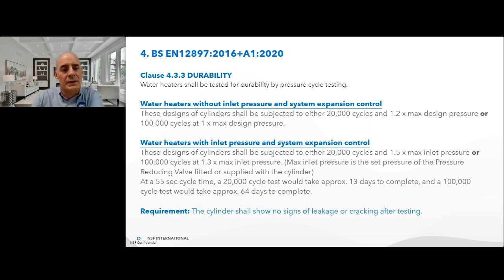So these are water heaters with inlet pressure and system expansion control. These designs of cylinders should be subjected to either 20,000 cycles at 1.5 times the maximum inlet pressure or 100,000 cycles at 1.3 times the maximum inlet pressure. Maximum inlet pressure is the set pressure of the pressure reducing valve fitted or supplied with the cylinder. At a 55-second cycle time, a 20,000 cycle test would take approximately 13 days to complete, and a 100,000 cycle test would take approximately 64 days to complete. The requirement of the test then is that the cylinder should show no signs of leakage or cracking during or after test.